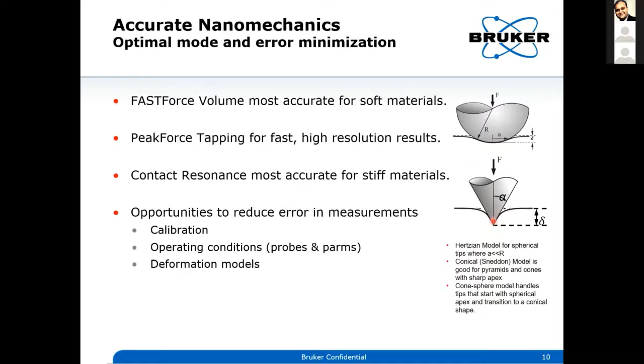Then you also have to calibrate every time, because every probe is unique: the spring constant of the probe is going to be different, and the tip is going to be slightly different from one to another, right? I will not go into too much detail, but the major error in the evaluation of your modulus comes from the estimation of the tip radius and the estimation or calculation of the spring constant. So these two play the major part, and it is very important to get them right.